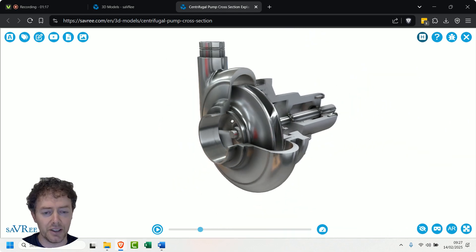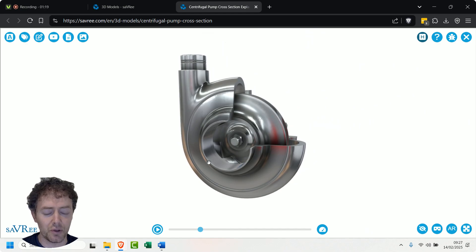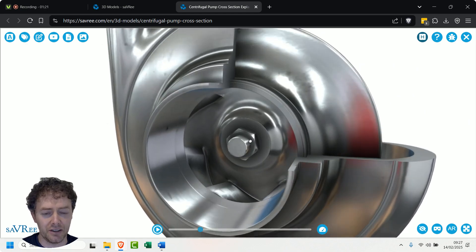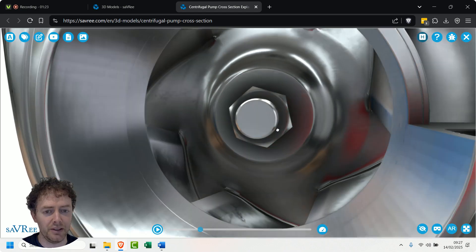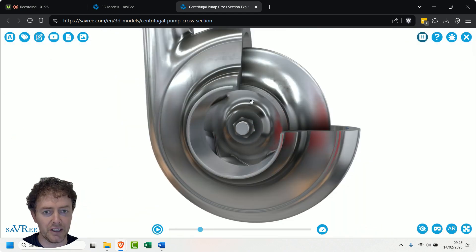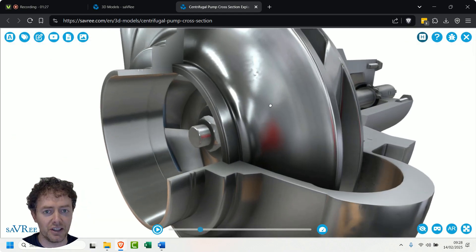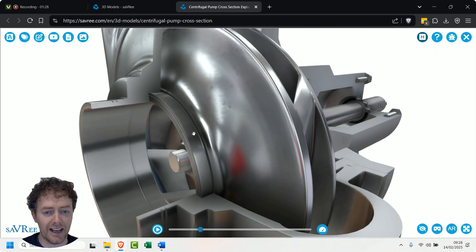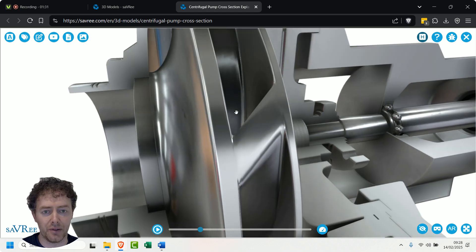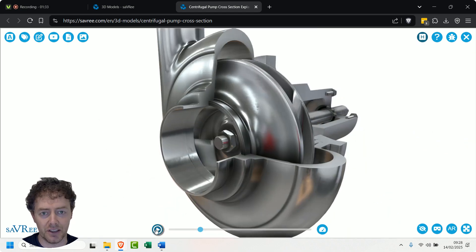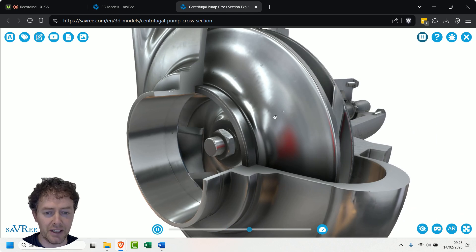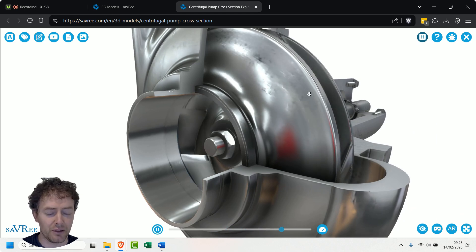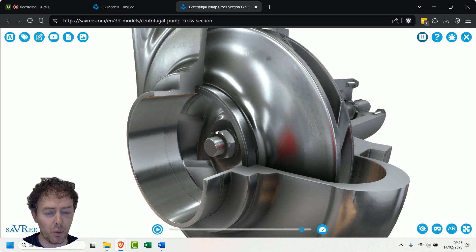So essentially what this is doing: it's drawing in fluid in through this gap here, it's going to be drawing that fluid in and then it's going to discharge it radially outwards, so it comes out the side of the impeller. So let's just see how it does that. The impeller rotates, it's throwing the fluid outwards radially away from the center axis of rotation.